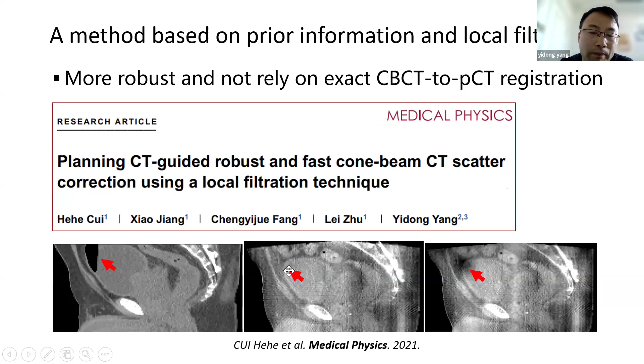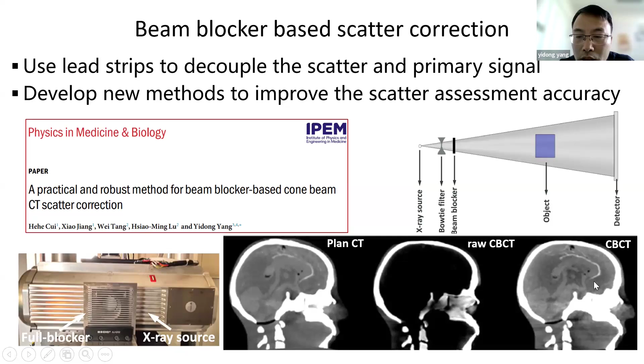Another way is to use hardware to improve the image quality and reduce the scatter. We designed these lead blocks, which are also kind of lead strips, so they can block most of the scatter. After the beam goes through these gaps, we think most of the signal is direct beam signal with minimized scatter. Then by subtraction, we can calculate the scatter, and subtract the scatter from the cone beam CT projection to get a better cone beam CT image.